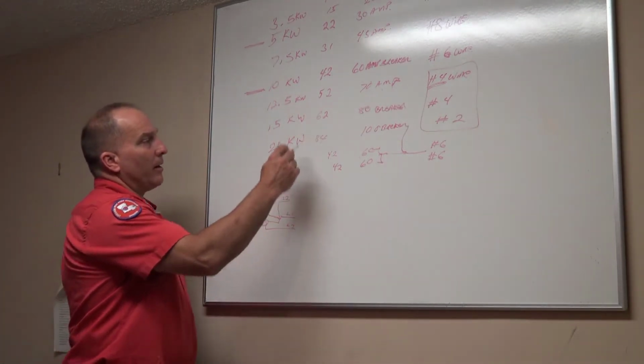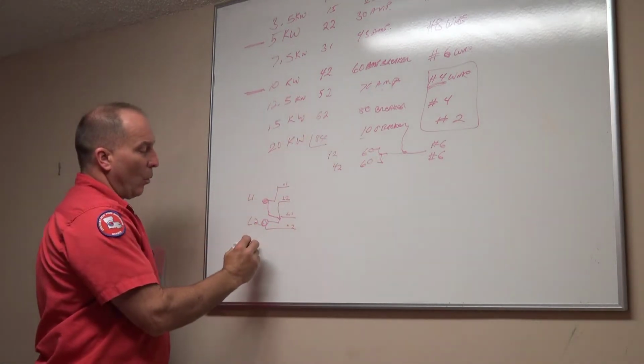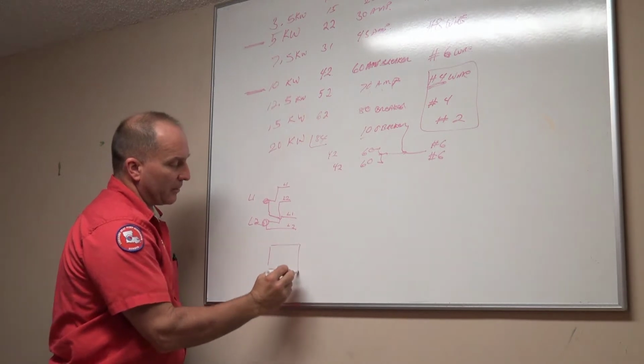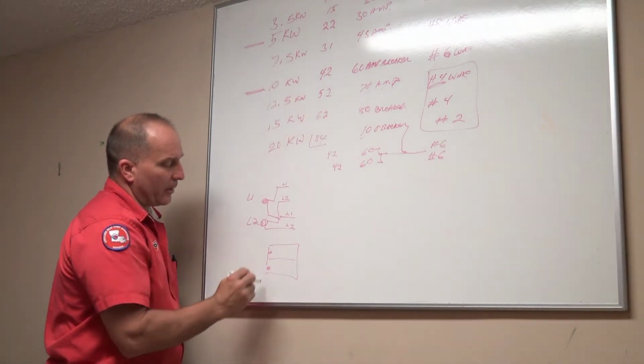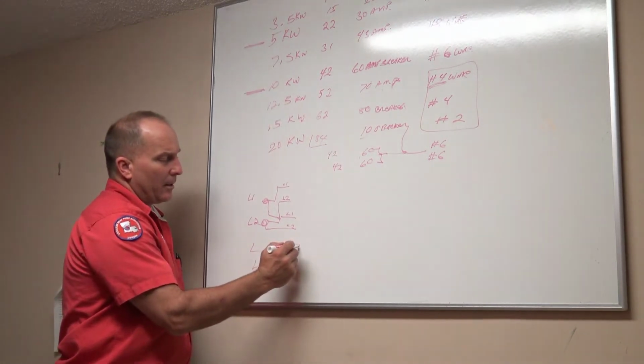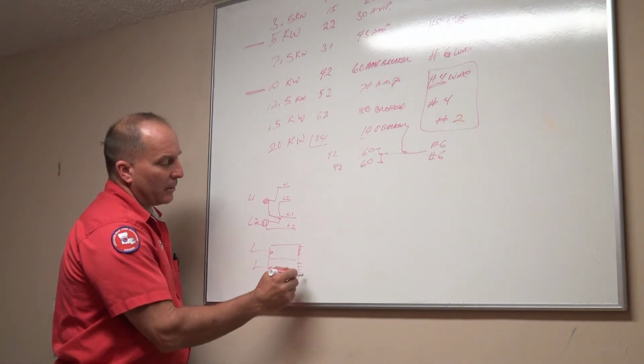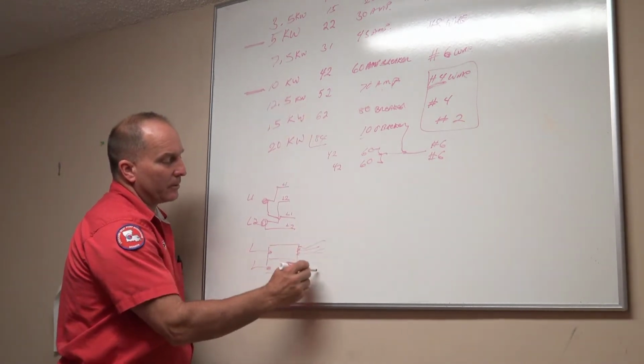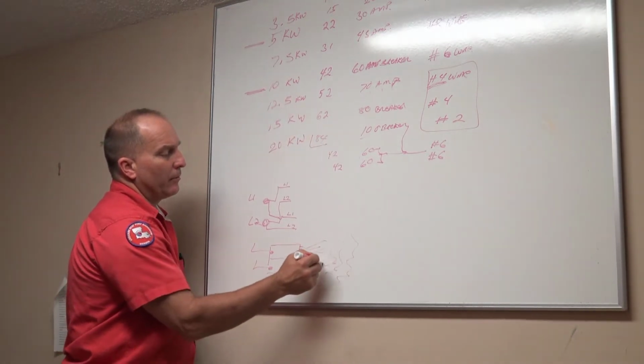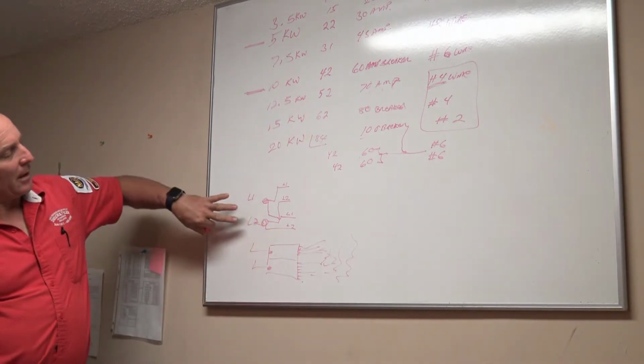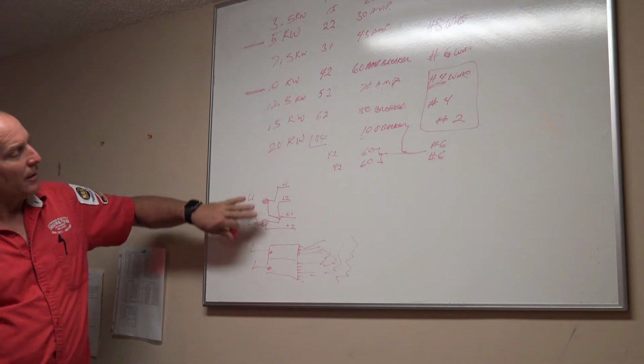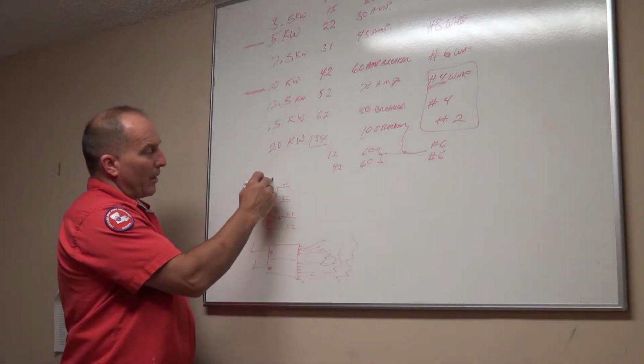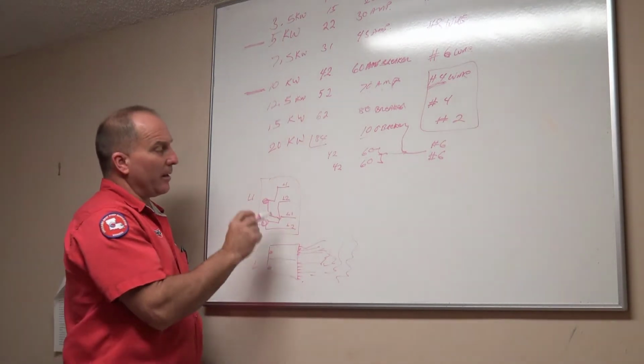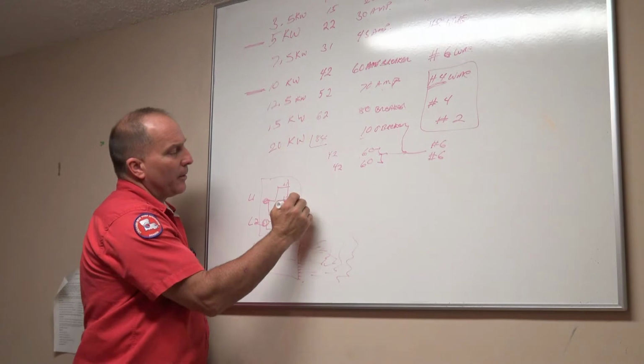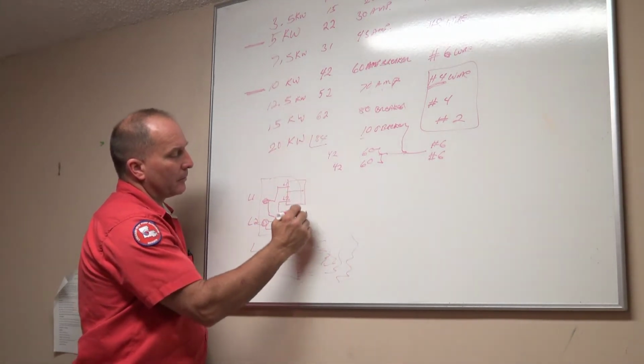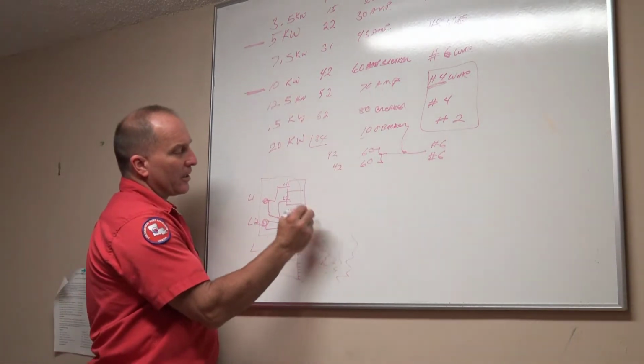Or you have one 100 amp breaker, and if you've got one 100 amp breaker, then you have one breaker like this. Terminal here, right? L1, L2. And then your spades on the back of it do what? Your heating elements are tied into here, L1, L2. Run through your heating elements, right? 2, 3, 4, boom. And that feeds one. Or you do it like this with one wire inside the air handler, and then you have this metal terminal block basically that you put in there, and this literally screws into breakers. And then these breakers go into your system.